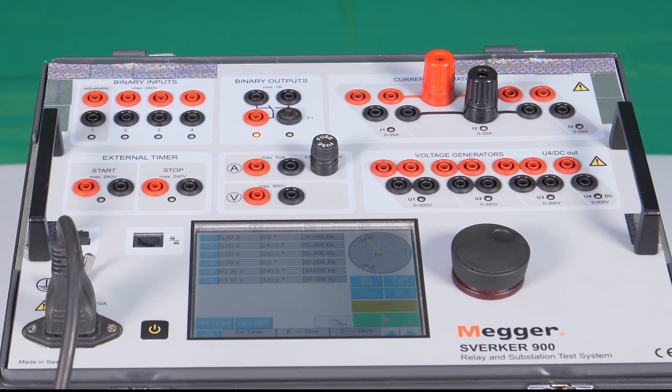By connecting the circuit breaker trip command from the relay to timer start and the 52A contact of the circuit breaker, the dead time can be recorded. The external timer can be saved as part of the report for future records by enabling the option available here.